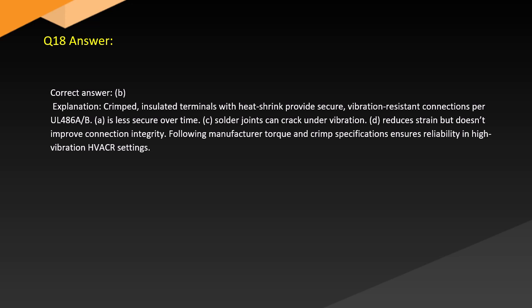Answer. Correct answer: B. Explanation: Crimped insulated terminals with heat shrink provide secure, vibration-resistant connections per UL. A. Is less secure over time. C. Soldered joints can crack under vibration. D. Reduces strain, but doesn't improve connection integrity. Following manufacturer torque and crimp specifications ensures reliability in high-vibration HVACR settings.